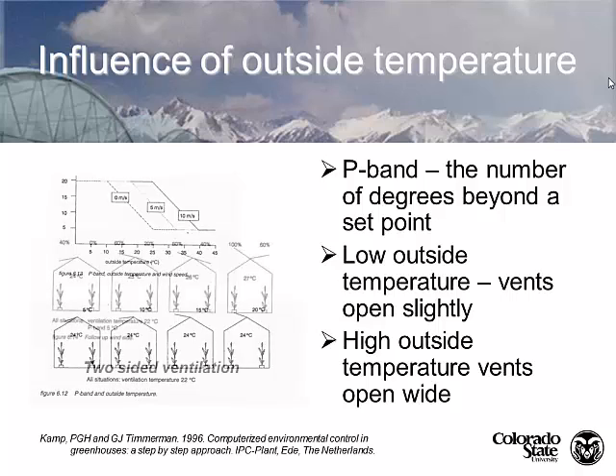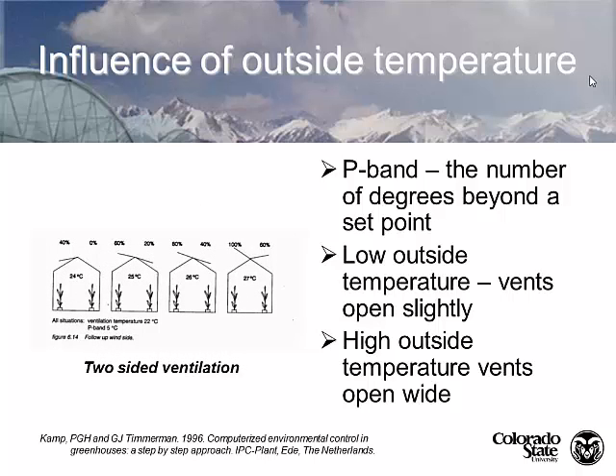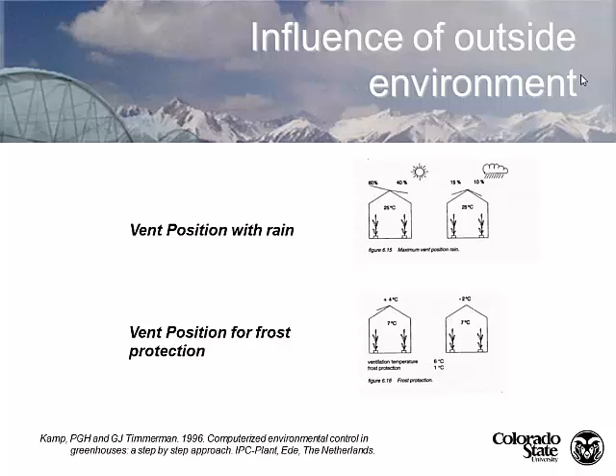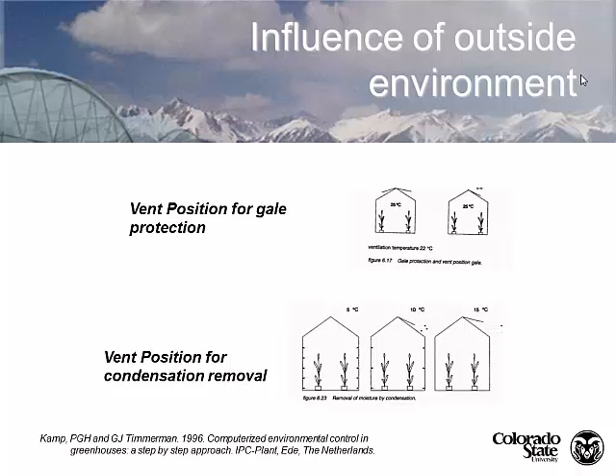With two-sided ventilation, depending on the direction of the wind, you may want to open one side 100% — that could be the leeward side — and on the windward side you may only open it 5–10% so the wind isn't as likely to rip the roof off. For frost protection you can make other differentials, based on whether it's raining or not. For gale protection you may want to think about leeward versus windward side, or closing vents entirely and turning on the fans.